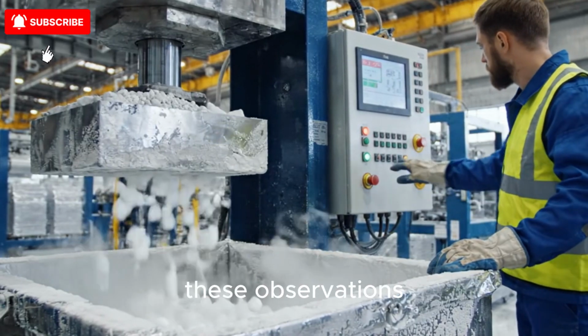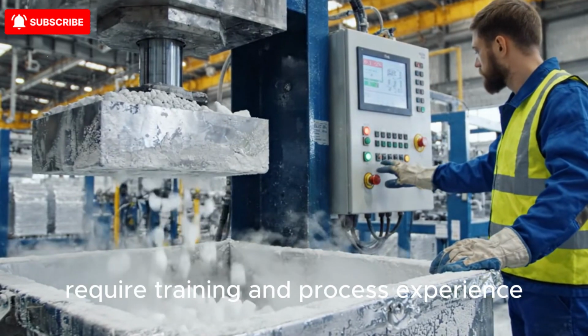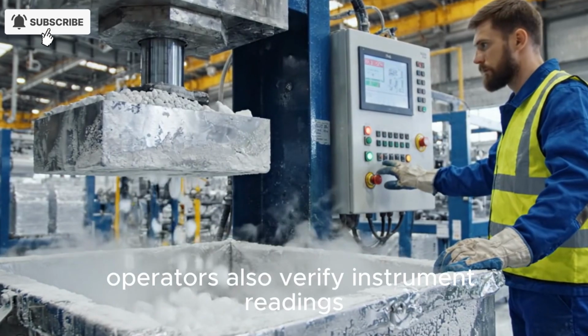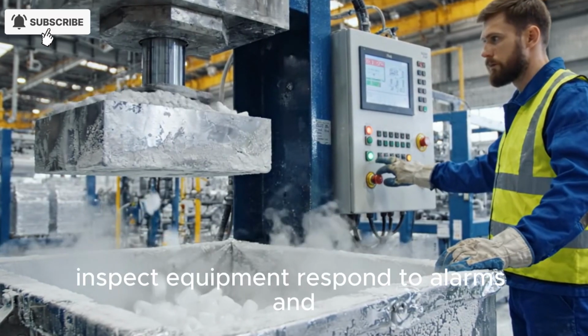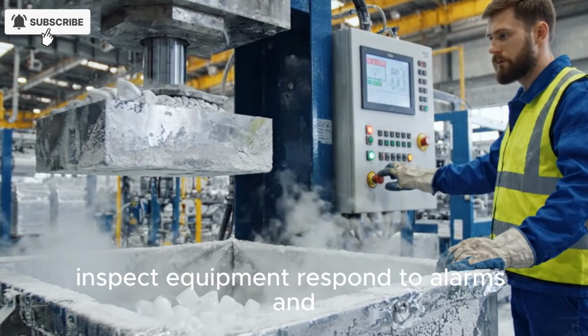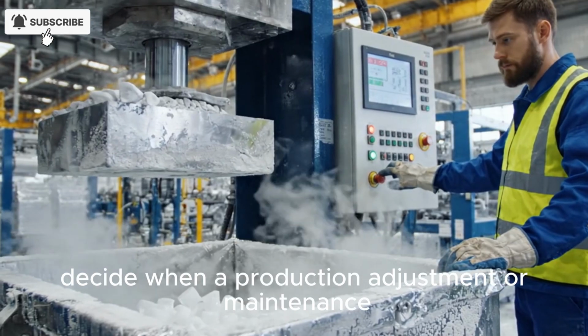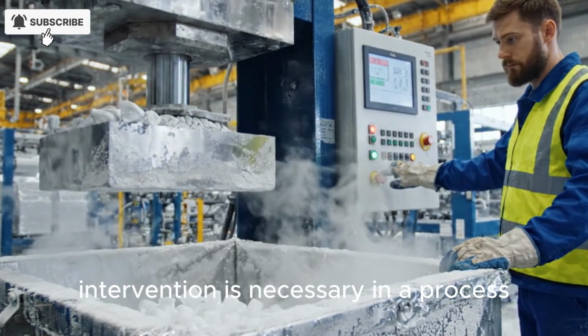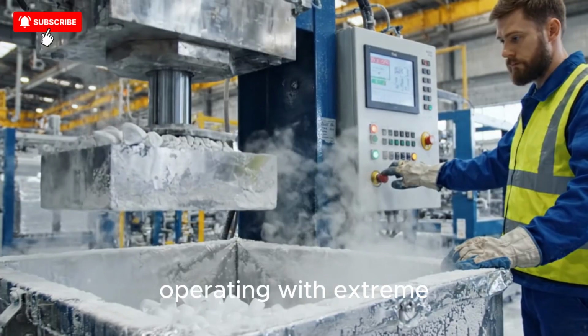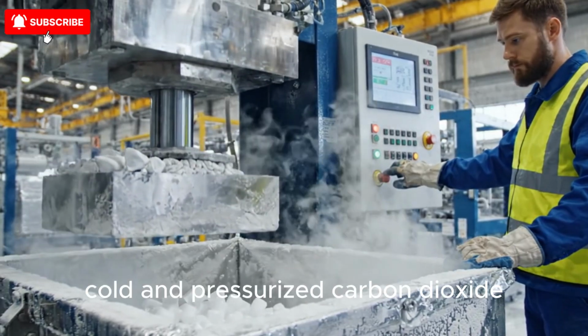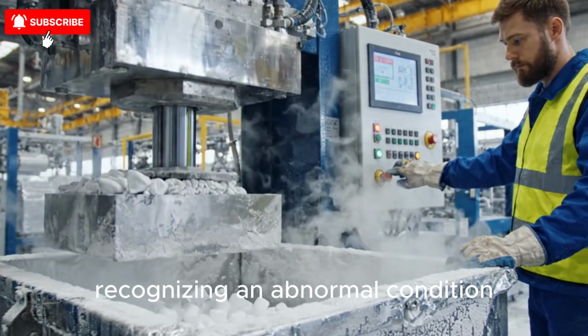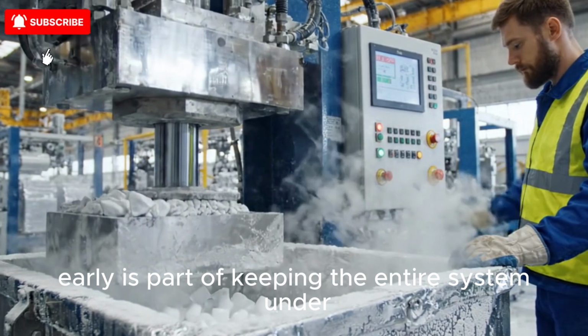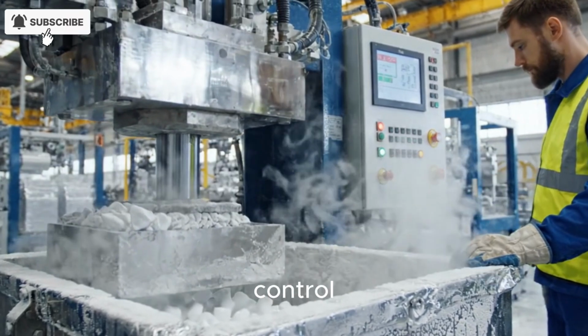These observations require training and process experience. Operators also verify instrument readings, inspect equipment, respond to alarms, and decide when a production adjustment or maintenance intervention is necessary. In a process operating with extreme cold and pressurized carbon dioxide, recognizing an abnormal condition early is part of keeping the entire system under control.